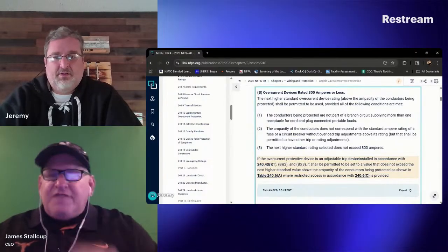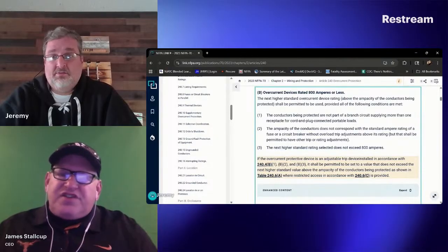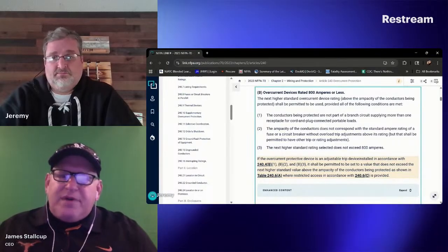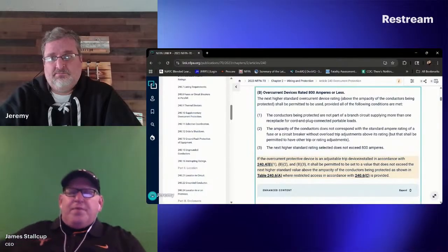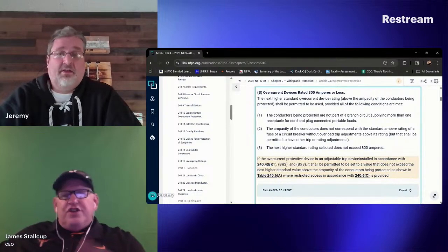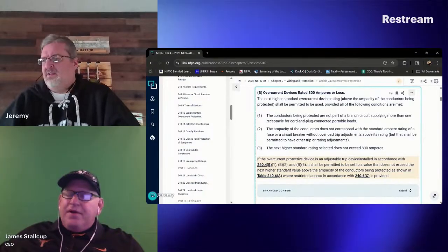I mean, now if I go up to a 65 amp number 6 conductor and it's good for 65 amps, can I put a 70 amp on there? Sure can. Okay. Now you learned how to apply 240.4(B) correctly. I've been doing that my whole career. You just argued with it just now that I had to go up to a 70 amp. What?